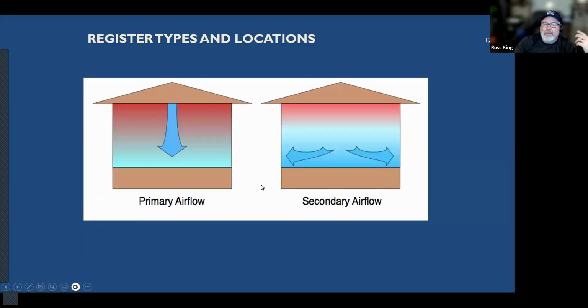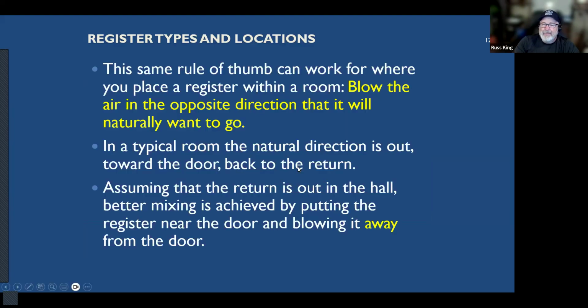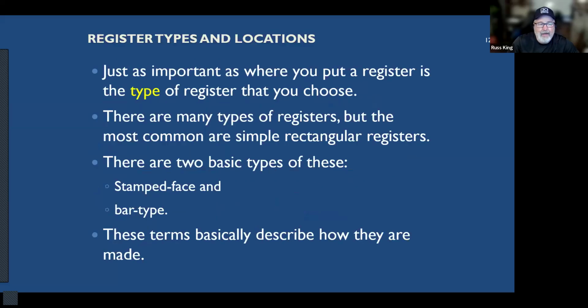Unfortunately, you can't have ducts for heating in the ceiling and ducts for cooling in the floor. You've got to pick one or the other and hope for the best. So blow the air the opposite direction that it wants to go. That's one of the most important things I can teach when I teach HVAC design: where to put a register in a house and things like that. By the way, I know I'm not going to be able to finish my slides. I almost never do in this class. You will get a copy of these slides, so you'll be able to finish up.